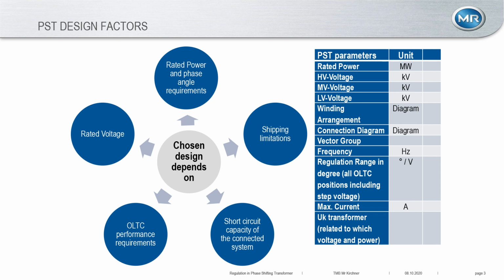And if we look at certain designs, especially single core designs, we will see that later on, if the on-load tap changer is moved to the K position, as we call it at MR, you have no reactance, no impedance in your power line anymore. So if you have certain limits for short circuits, it can be the case that you need an additional reactor, because in the K position, in the single core design, you don't have any impedance that would limit your short circuit. And on the right-hand side, you see a table as an example with certain inputs we need to come up with the proper OLTC.